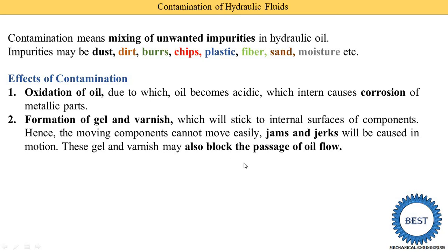The second effect is the formation of gel and varnish, which stick to the internal surfaces of components, so moving components cannot move easily. This causes jerky or stuck motion. Additionally, gel and varnish may block the passages of oil flow, so oil is not supplied to the full system and the system stops.